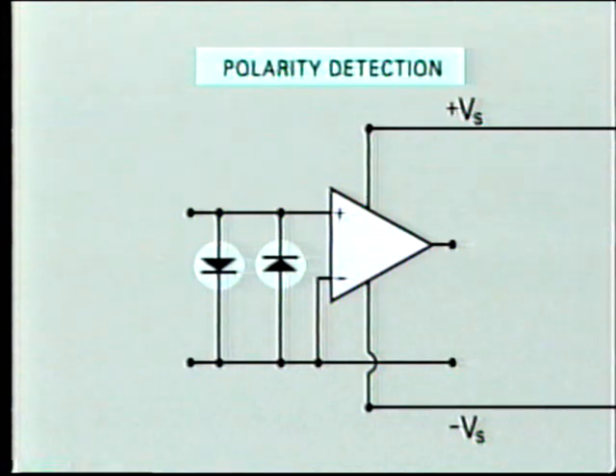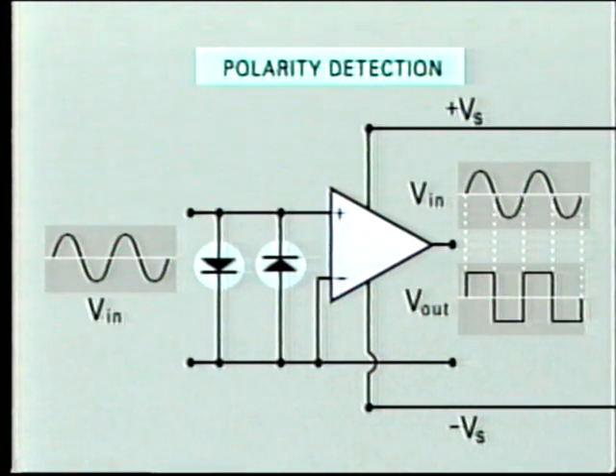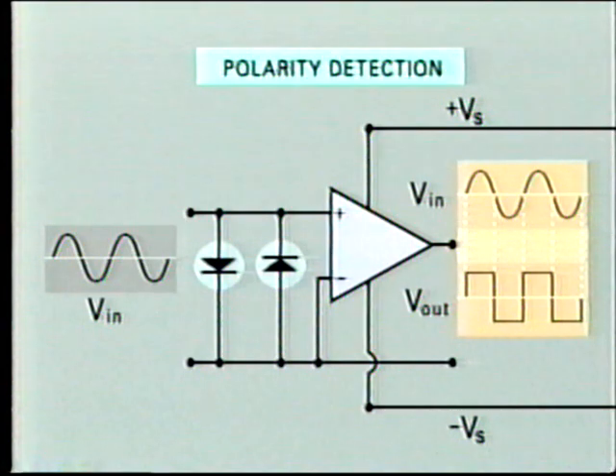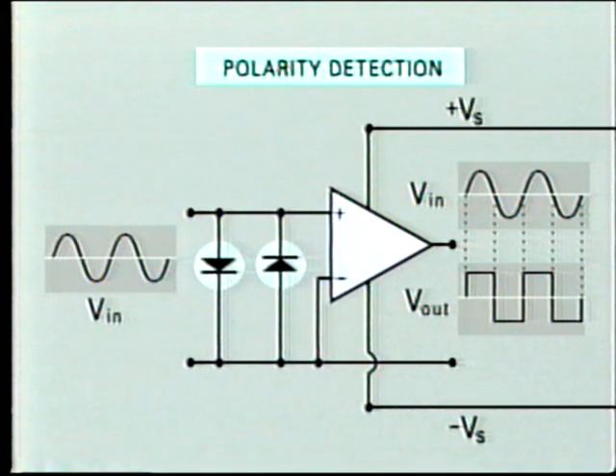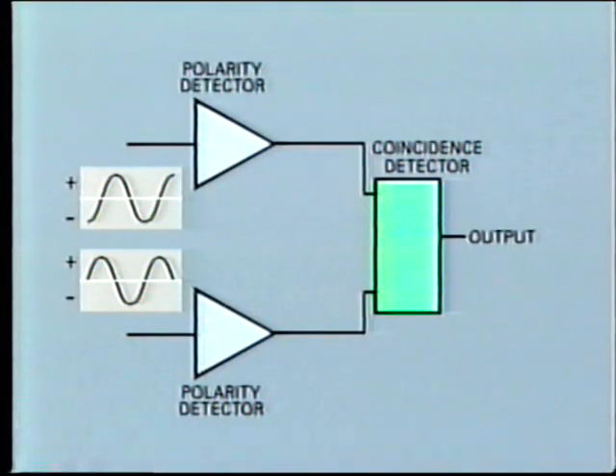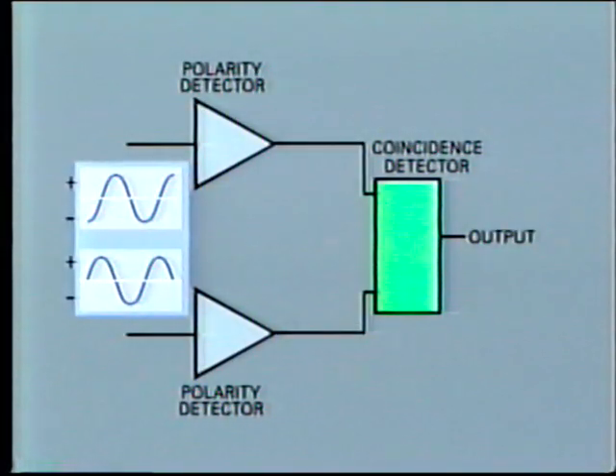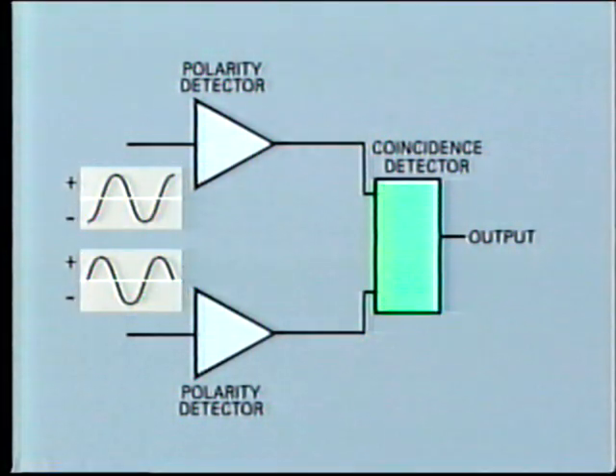Let's take a look at polarity detectors. This diagram shows us the integrated circuit arrangement. The essential feature of this circuit is that the output is in phase with the input, but it's in the form of a square wave. This makes it easy to detect precisely when the sine wave crosses the 0 point. One of the main uses of polarity detectors is to measure the phase difference between two sine waves from two different sources. Phase comparison is used for directional relaying, which is required in many types of protection schemes.